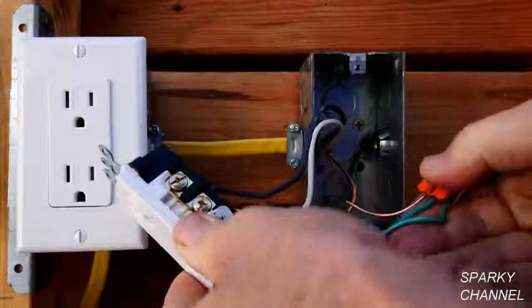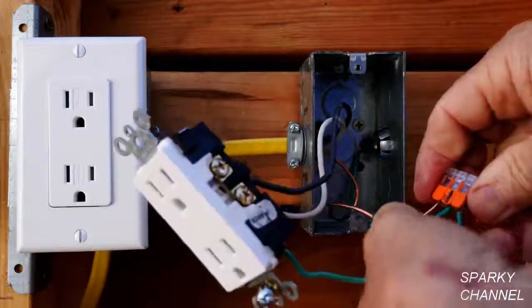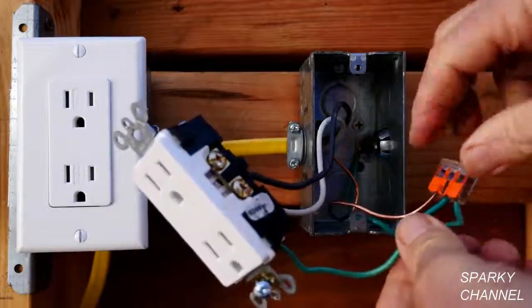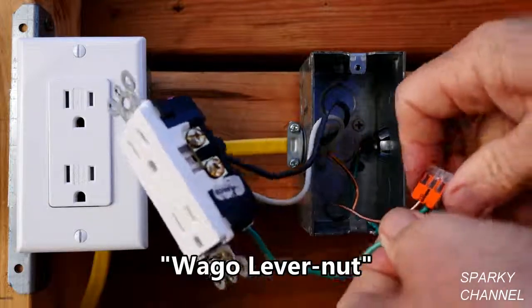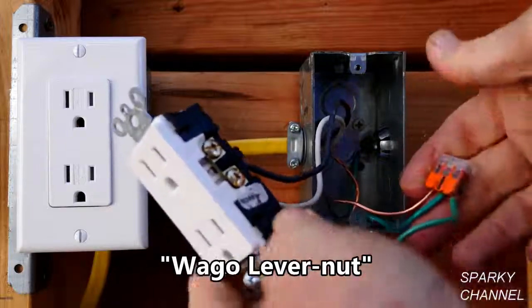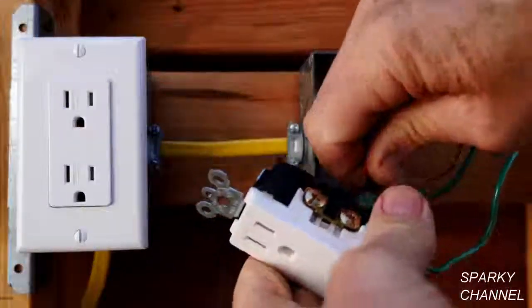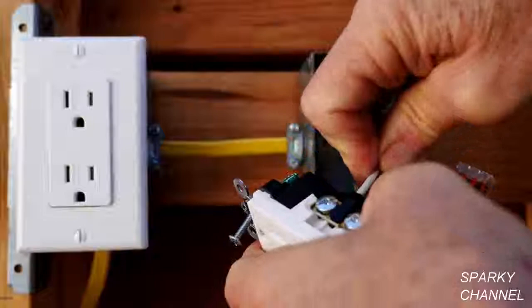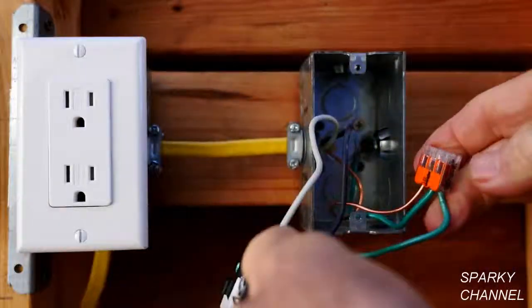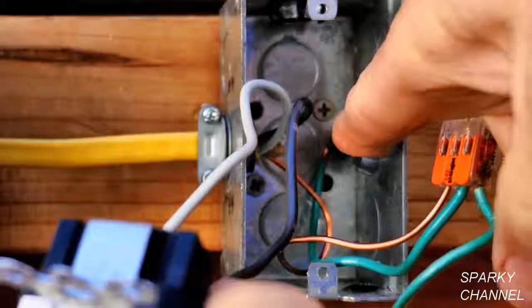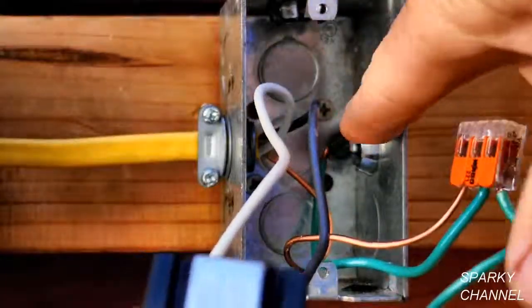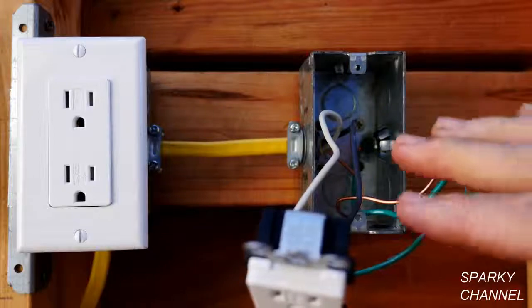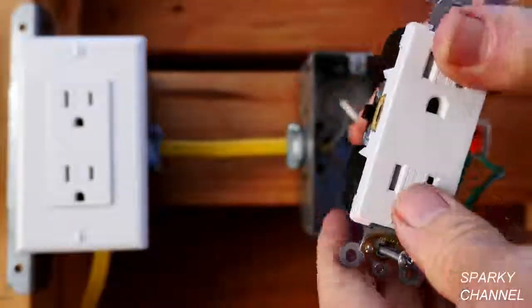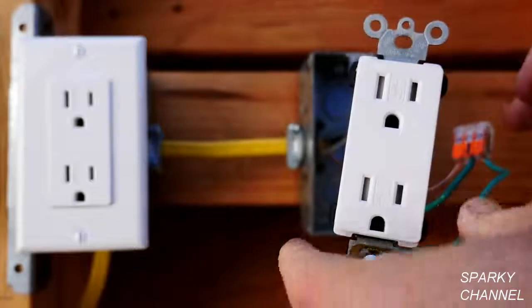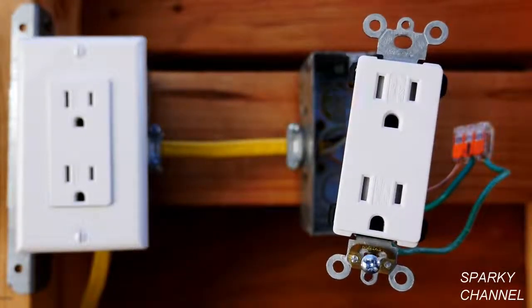Okay, we'll give all the grounds in the lever nut here. This is called a Wago lever nut. I give them all a tug and make sure they're tight. They're all tight. Okay, I'm going to check, make sure this neutral wire is tight. It is. Okay, the metal box is bonded back there. You see a bonding screw. Everything seems proper in this box. I'm not finding any problem at all in this box. I don't see why it would be a problem here.